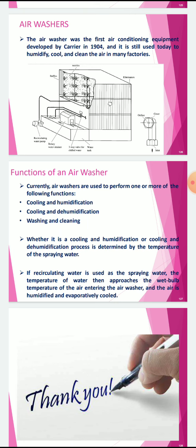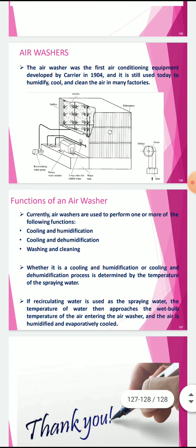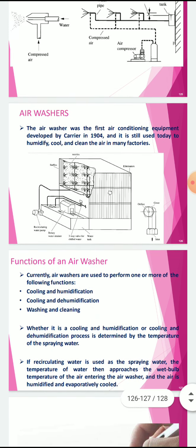If recirculating water is used as the spraying water, the temperature of water then approaches the wet bulb temperature of the air entering the air washer, and the air is humidified and evaporatively cooled.